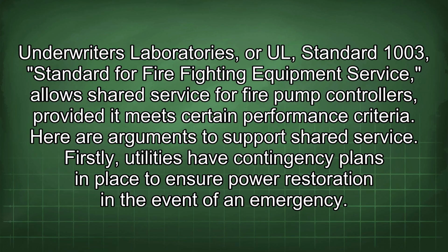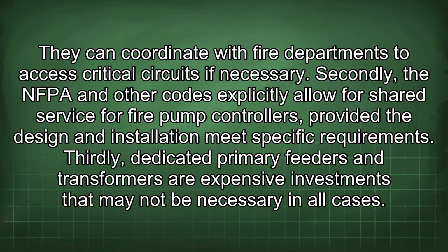Firstly, utilities have contingency plans in place to ensure power restoration in the event of an emergency. They can coordinate with fire departments to access critical circuits if necessary. Secondly, the NFPA and other codes explicitly allow for shared service for fire pump controllers, provided the design and installation meet specific requirements. Thirdly, dedicated primary feeders and transformers are expensive investments that may not be necessary in all cases.